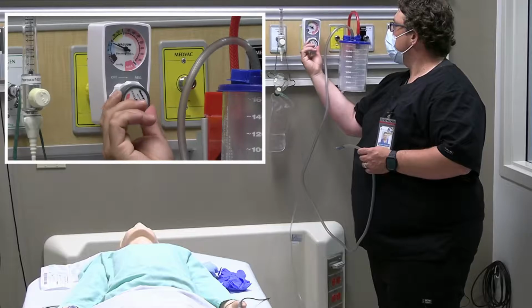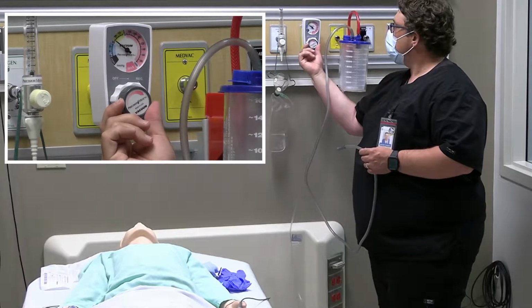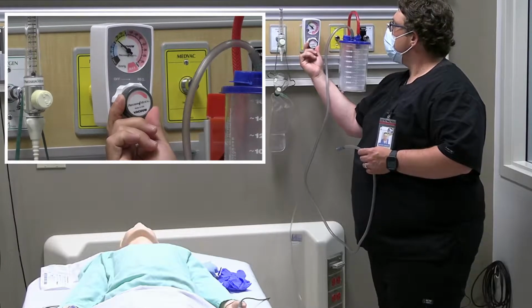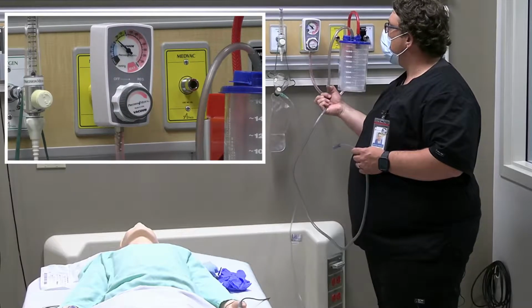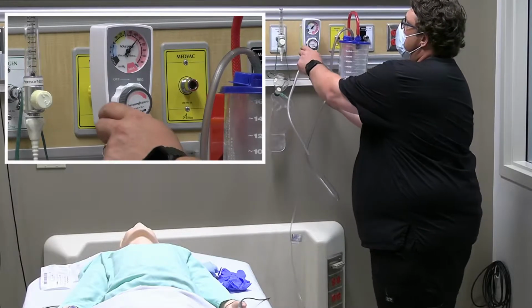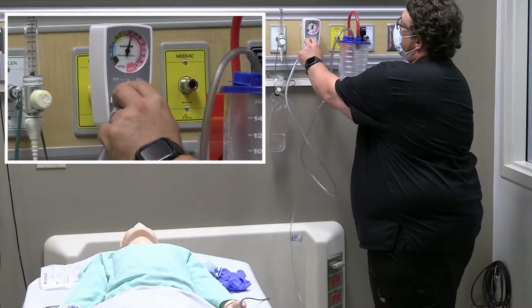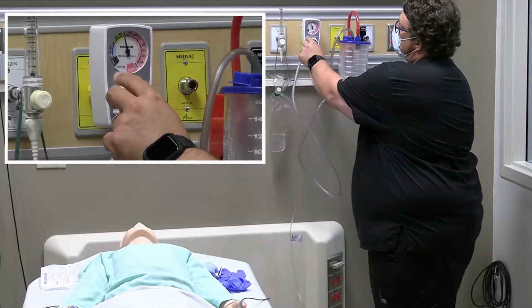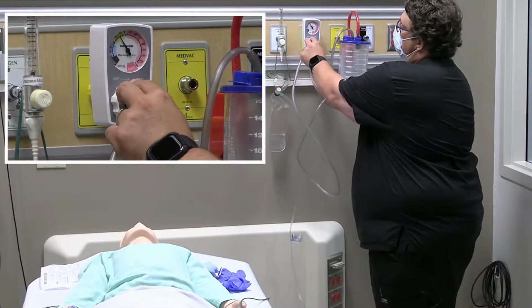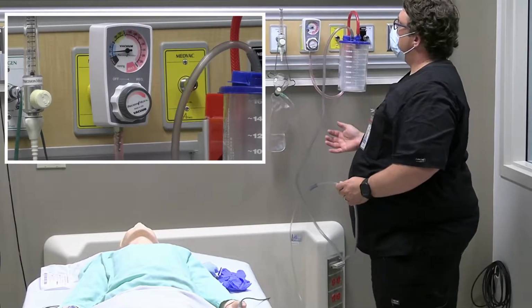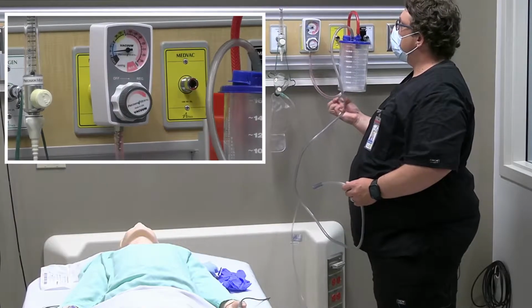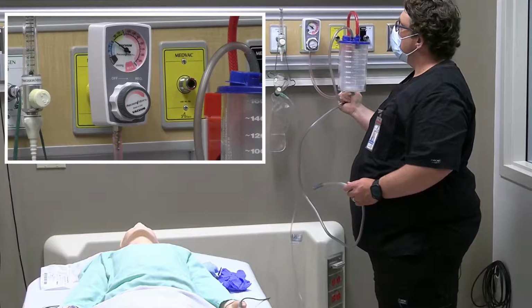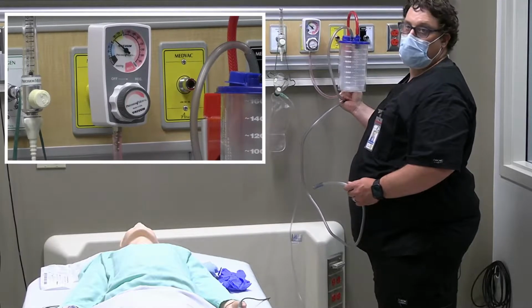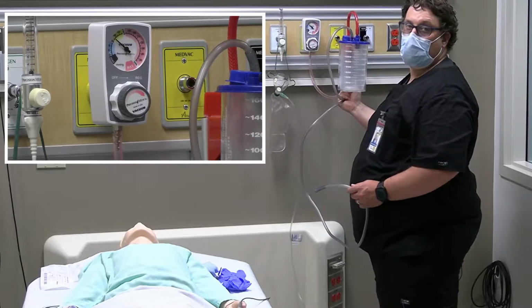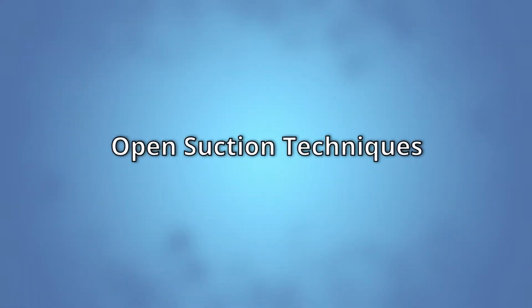So right now we're just below 80. I'm going to adjust that so that we're around 80, and then as I occlude my suction, it's a little bit too high. We want to stay in the medium range here, so I'm just going to dial that down. Once I remove suction and apply it back again, just to test it, we're now back up between 80 and 100 for our appropriate suction level.